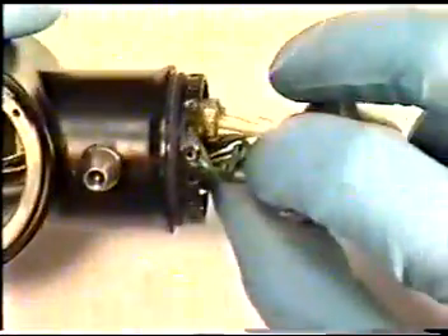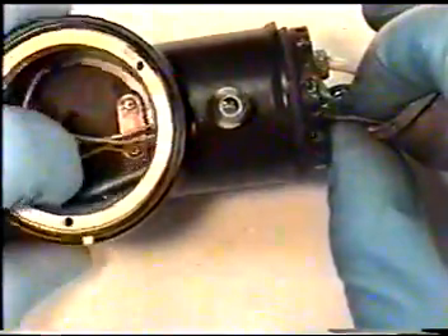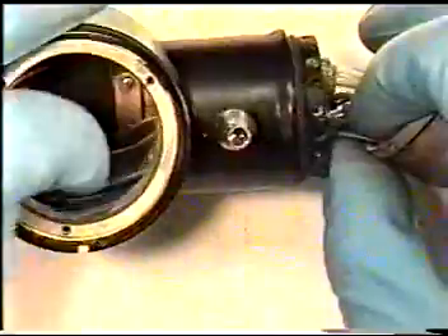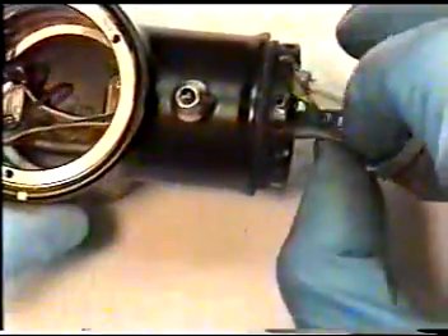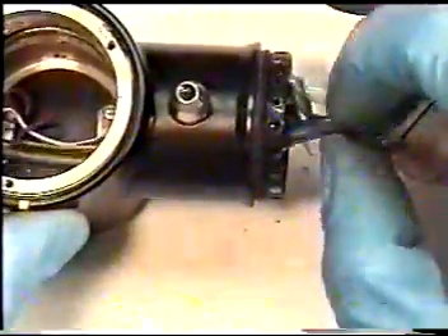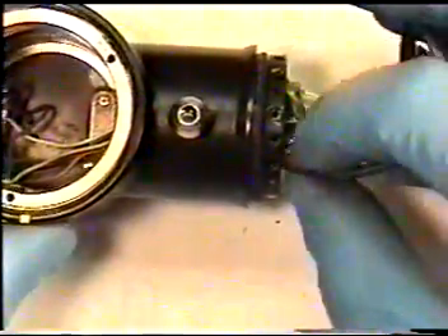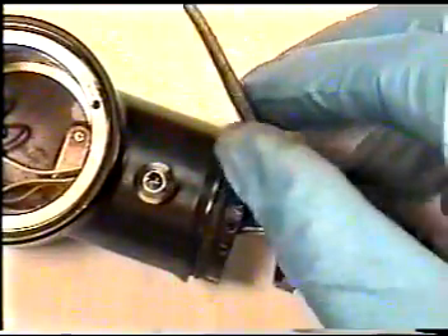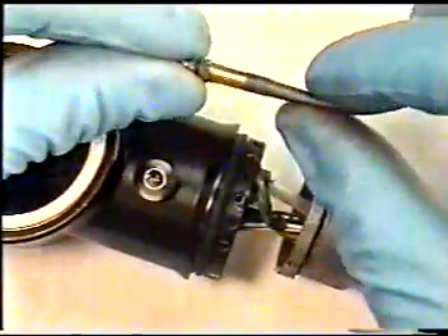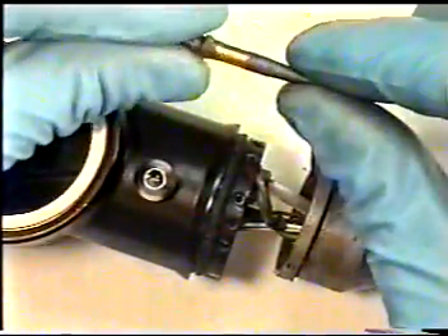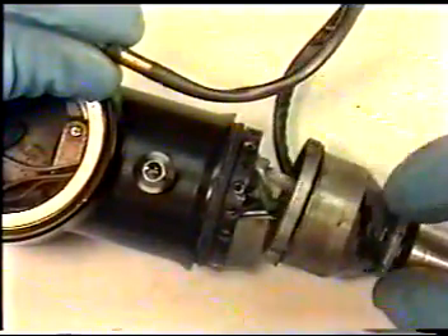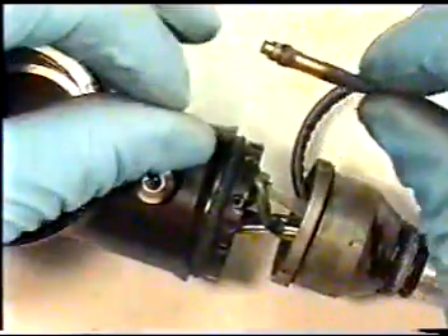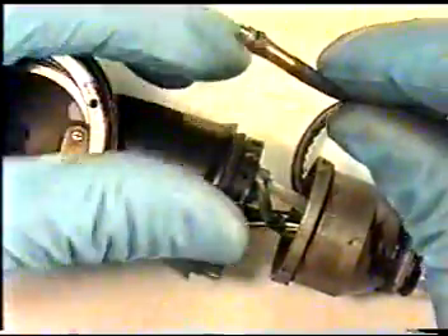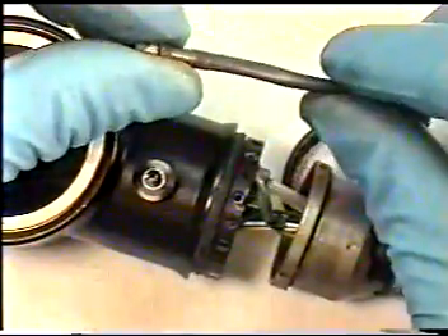We can now remove our damaged old light guide bundle, which was resting up against the side of this video connector. If this was a fiberscope, it would just pull out directly through the connector. Pull your light guide through. We'll need to attach another plastic tube on this light guide proximal fitting in order to pull through our light guide umbilical tube, in order to pull through our new light guide illumination bundle assembly.